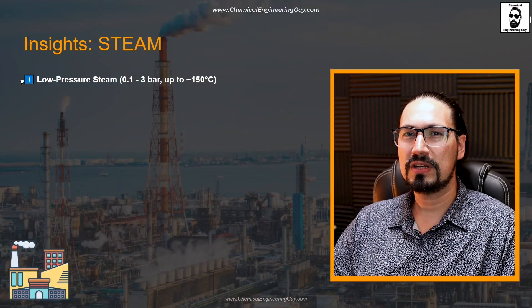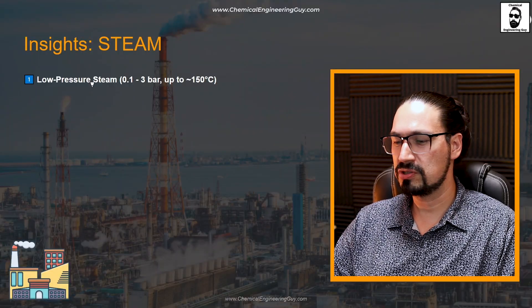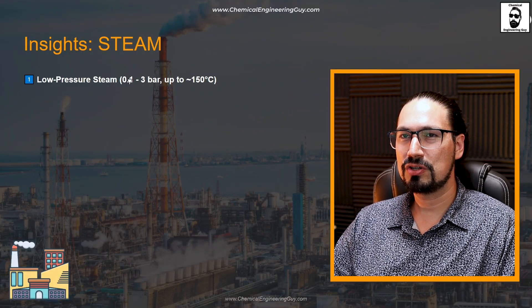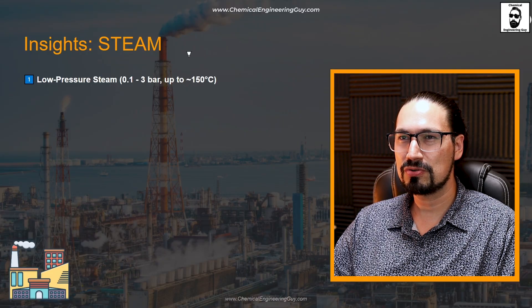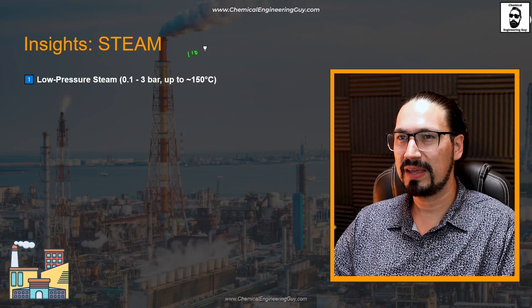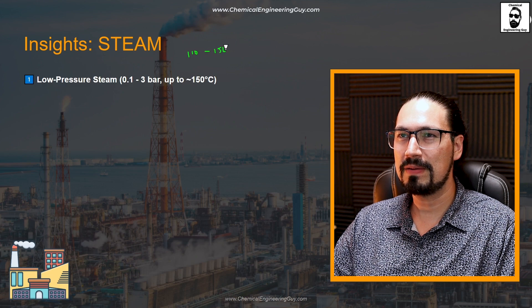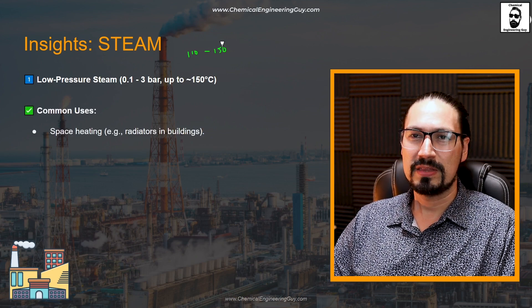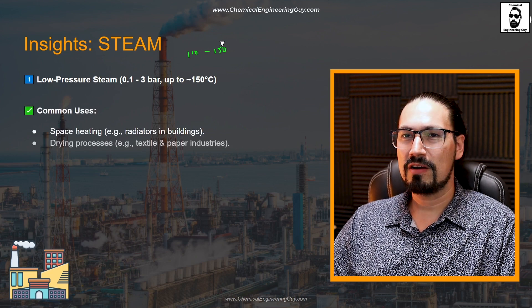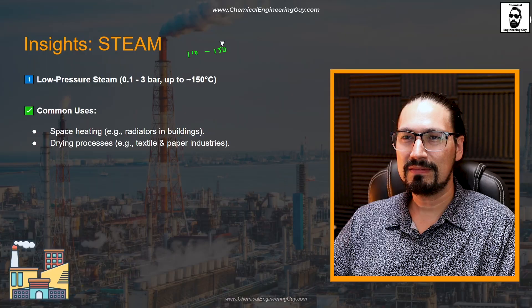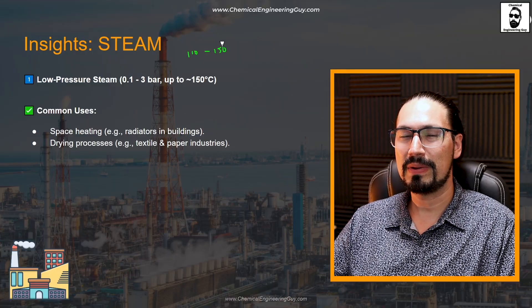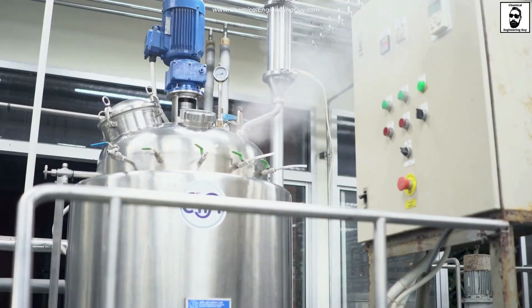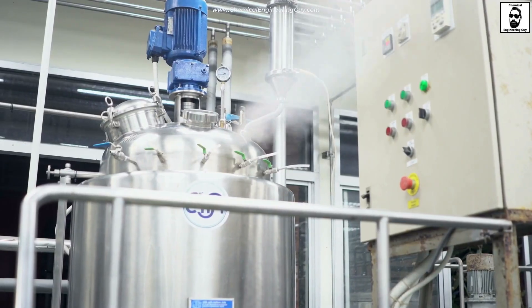We're going to focus our attention on low pressure steam, typically between 0.1 to 3 bars. Typical temperatures range from 110 all the way to 150 degrees. Once again, it really depends on the industry. Common uses include space heating and radiators in buildings, such as maintaining temperature in winter.